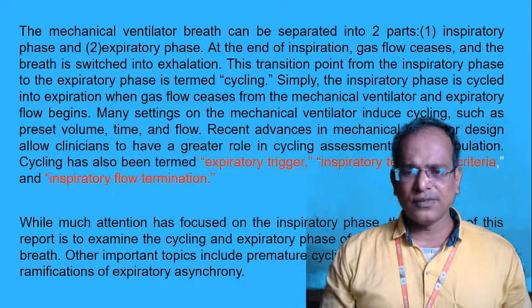So first we will see what the cycling mechanism is. The cycling of a mechanical ventilator breath occurs after a set value is reached. These values are often referred to as cycle variables. All the mechanical ventilator breath types are covered by the cycling variable. There are four variables used to determine when to cycle to exhalation: first one is pressure cycling, second is time cycling, third is volume cycling, and fourth is flow cycling.